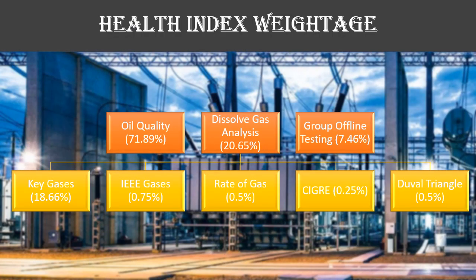We go deeper into the index or weightage. So we can see that there are 3 main important groups to identify the health index of the transformer. It is contributed by the oil quality, dissolved gas analysis, and the group of offline testings. You can see that dissolved gas analysis is the second highest among the 3, which contributed 20.65% of the overall computation of the transformer health index.